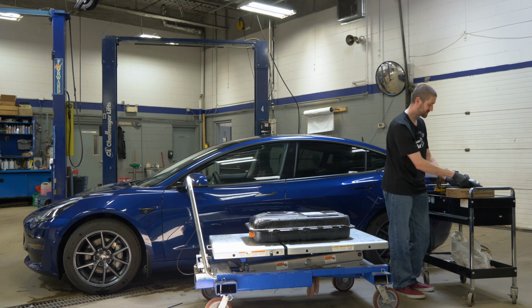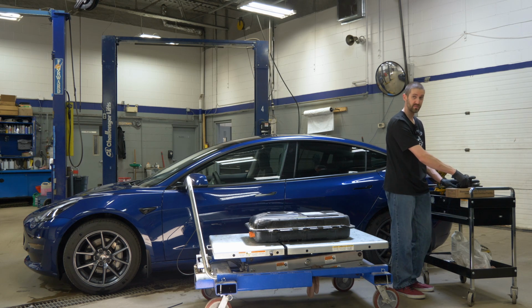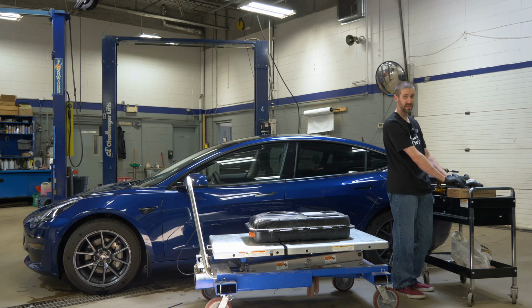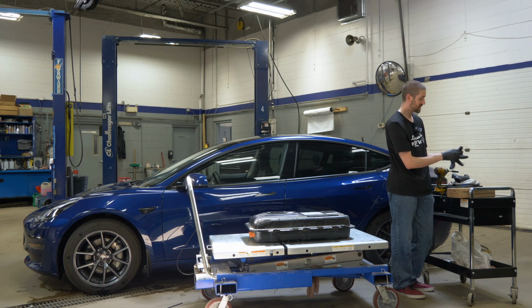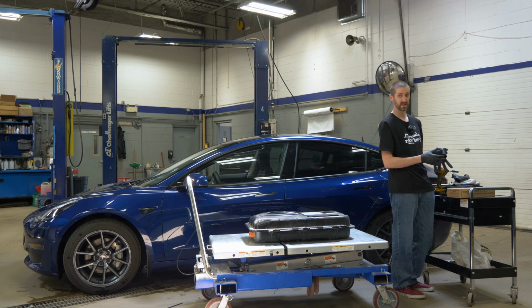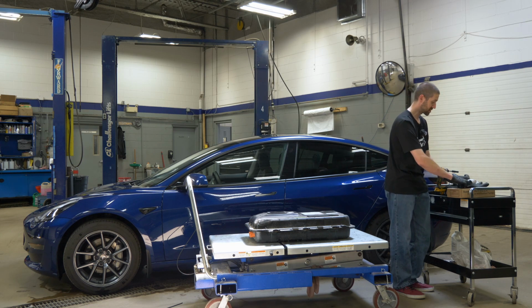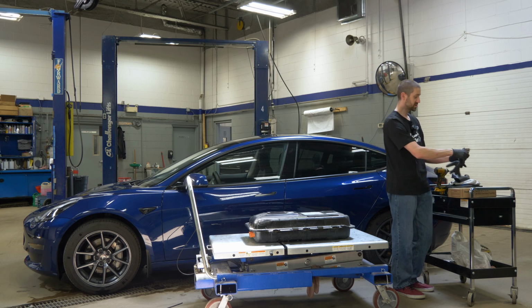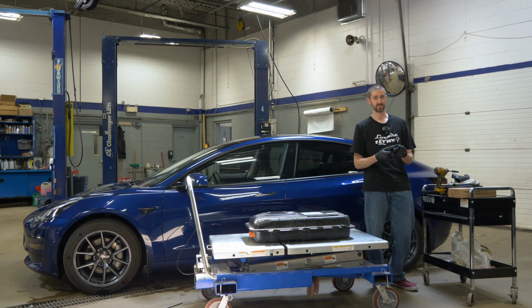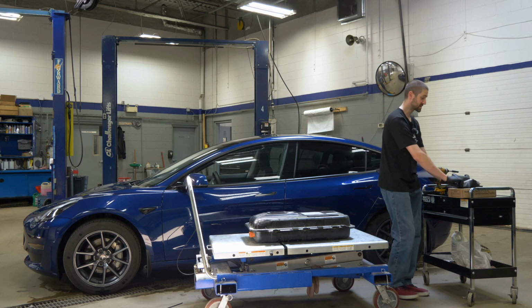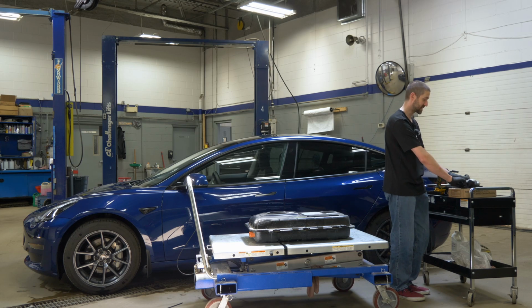So this test has to be done every single time you work with a high voltage component, because even a pinhole leak in these gloves will cause electricity to flow through them. And that's part of the reason why they get recertified every 6 months, is just to make sure that there are no pinhole leaks. They're also made out of natural rubber, and the problem with natural rubber is it does degrade over time, so that's another reason why we have to get these things certified. But it makes an excellent electrical barrier to keep us safe.